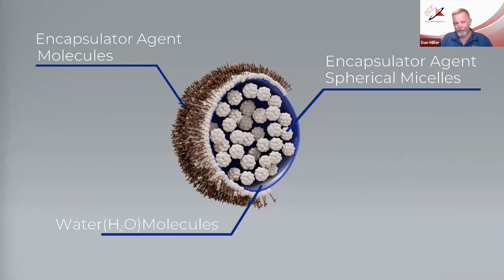Another factor is the modification of the water droplet's structure, with a coating of F500 molecules covering the outside—hydrophilic heads on the surface while hydrophobic tails point outward. This creates a very effective thermal circuit to absorb heat into the water droplet and then into the spherical micelles packed inside. Although the screen shows maybe 40 or 50 micelles, in actuality there are millions and millions of spherical micelles in each tiny water droplet, and each one readily absorbs heat, helping the droplet absorb heat very effectively.